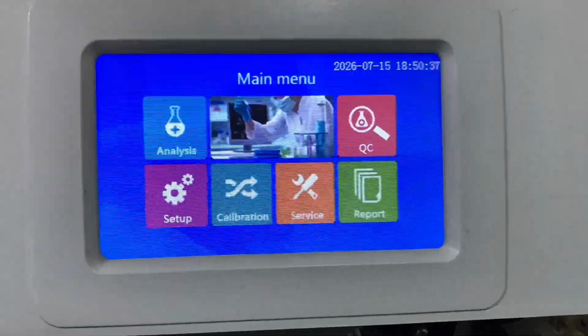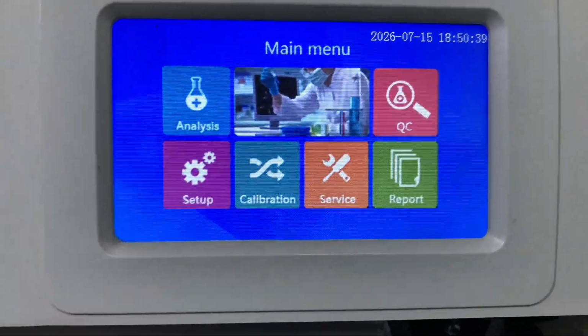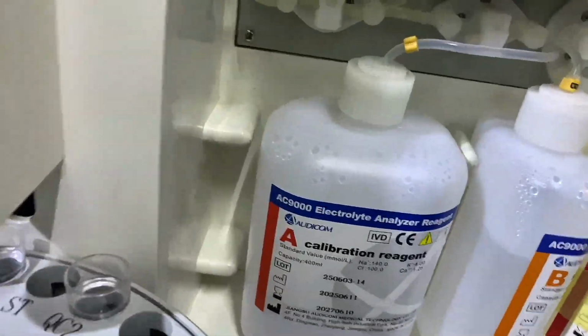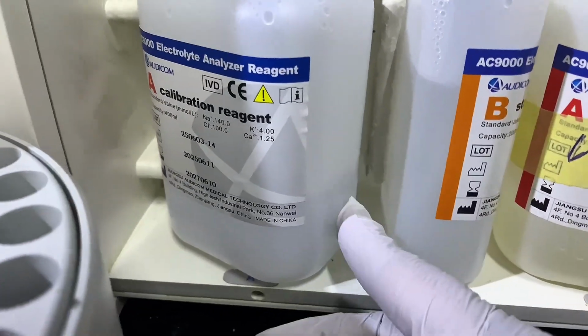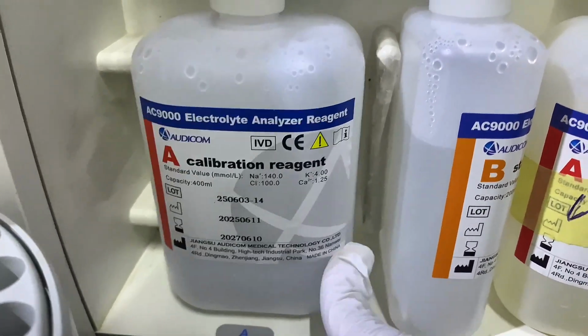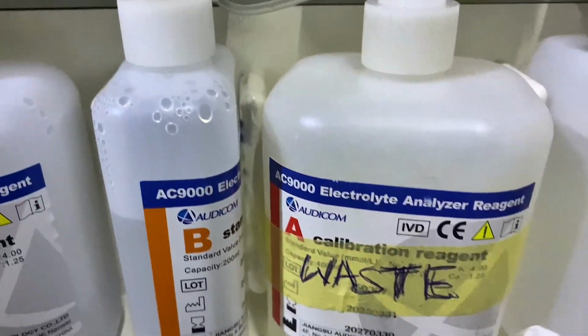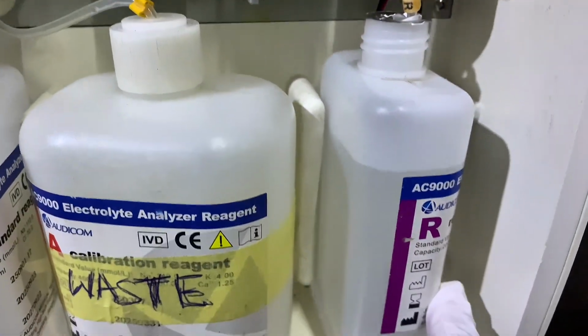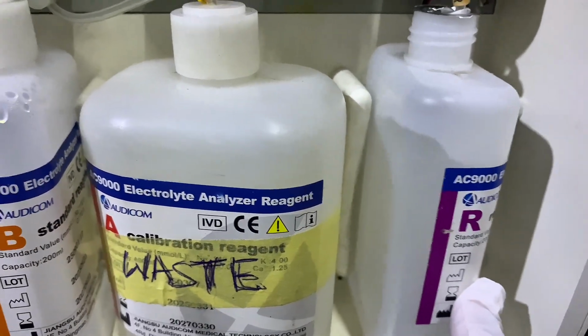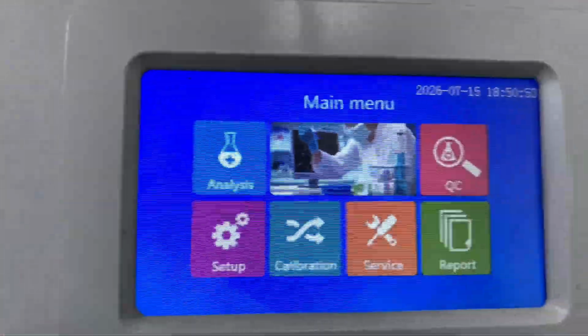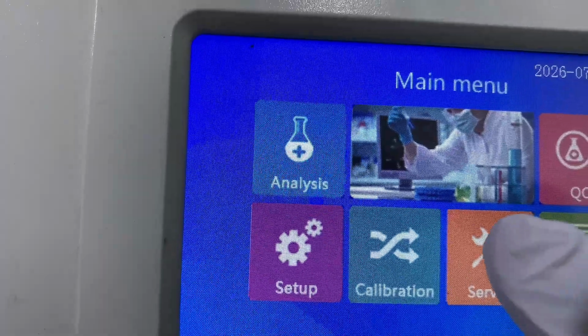When you put on the machine, it will take you to the main menu interface. Then you check if your reagent is enough and if the waste has been emptied. And this is an important step to take before carrying out your maintenance or running any tests. Then in the main menu, you click on service.